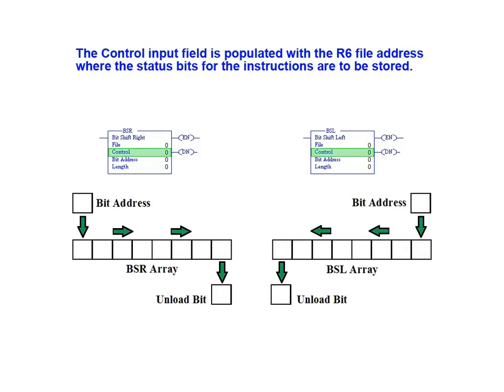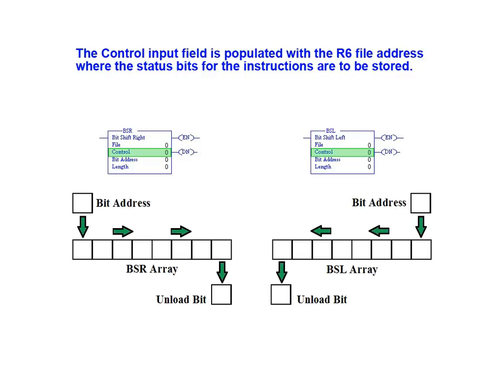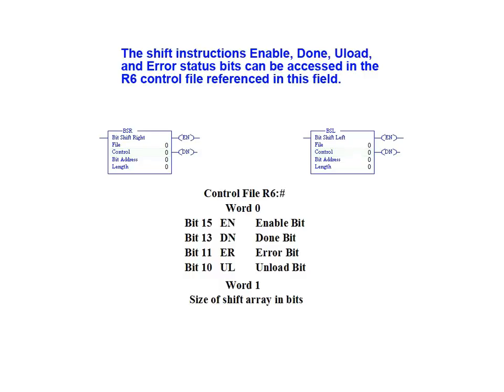The control input field is populated with the R6 file address where the status bits for these instructions are to be stored. The shift instruction's enable, done, unload, and error status bits can be accessed in the R6 control file referenced in this field. The bit address field is populated with the source location for the bit being shifted into each of these register instructions.